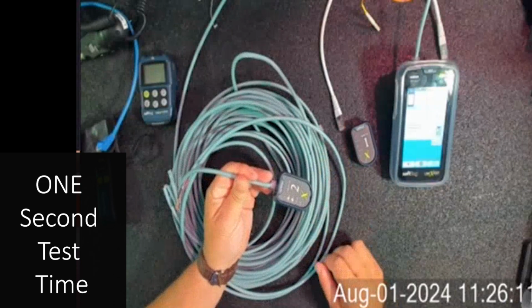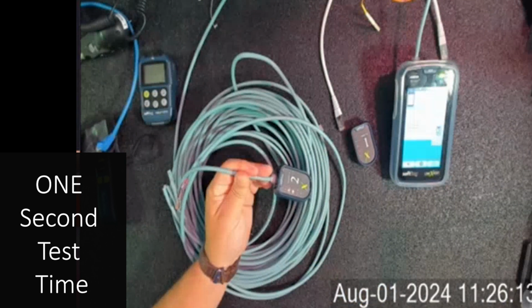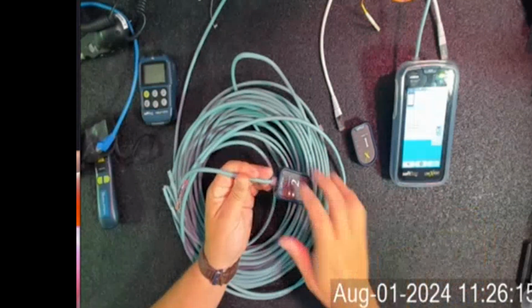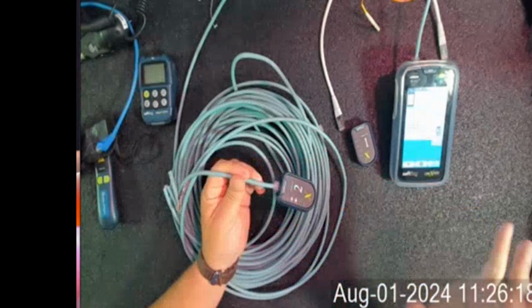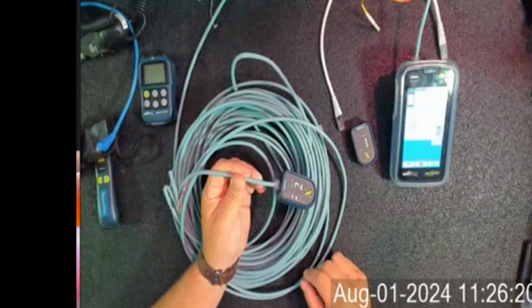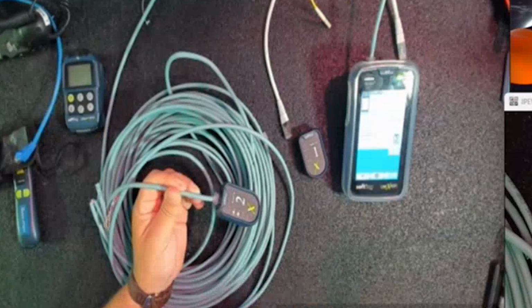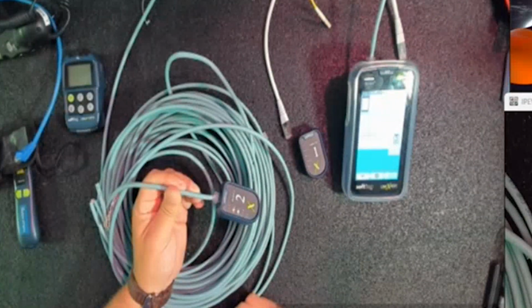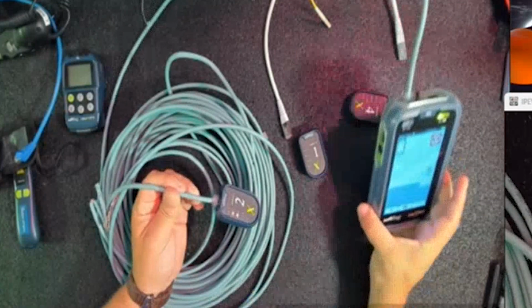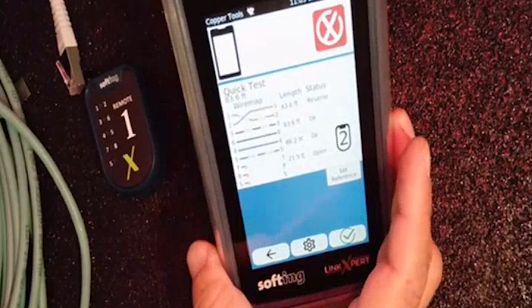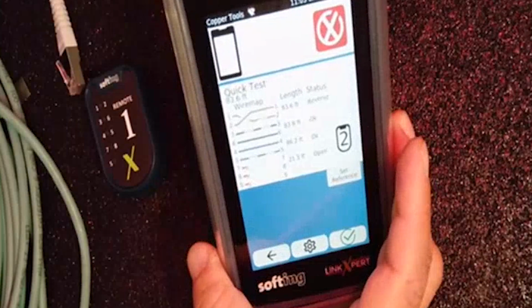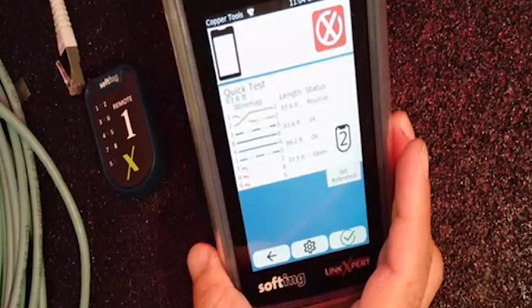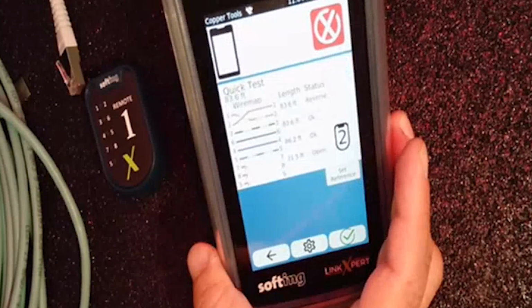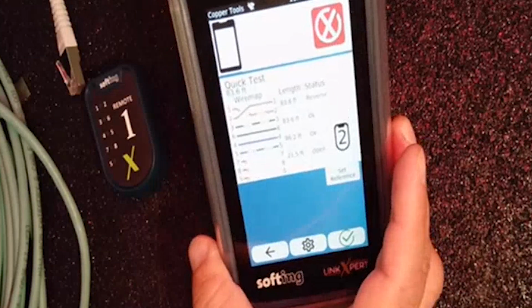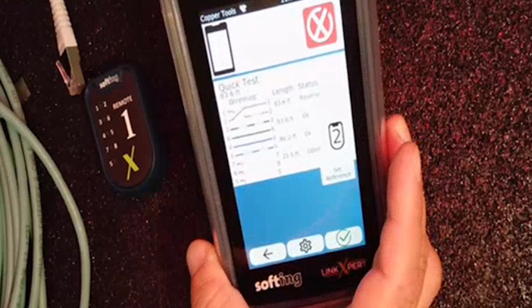Take a look at that result. I can see that I've got roughly 84 feet of cable here, so I get the length of not only the entire cable but each individual pair. It's telling me my 1-2 pair is reversed, showing that clearly on the tester. It's telling me 3-6 is okay, 4-5 is okay, and giving me the length of those individual pairs. Then look at pair 7-8 - it's open, and it's showing that in the display.